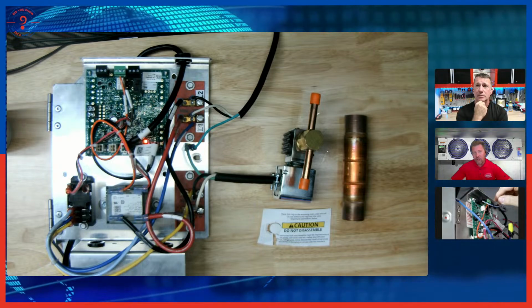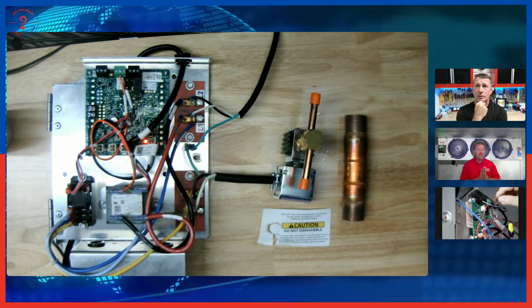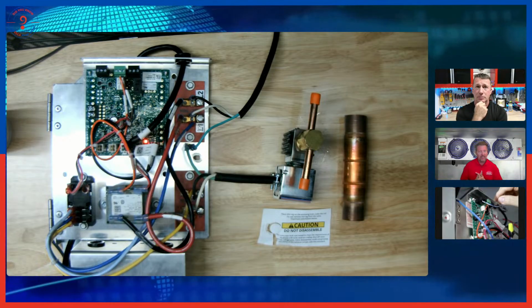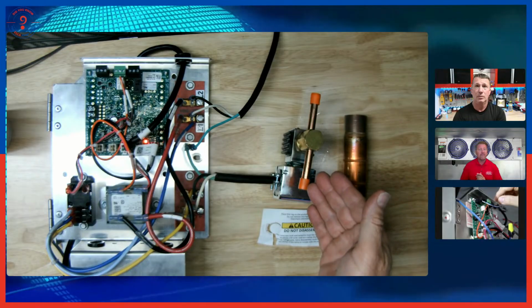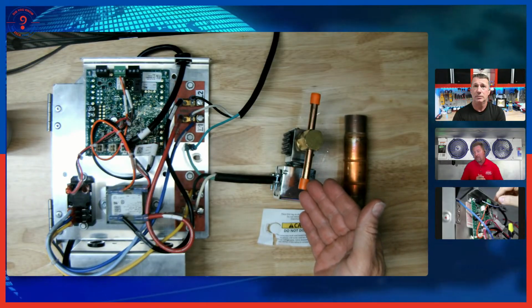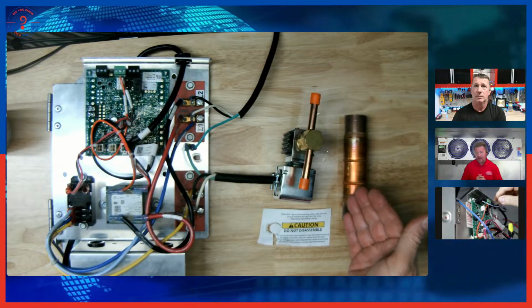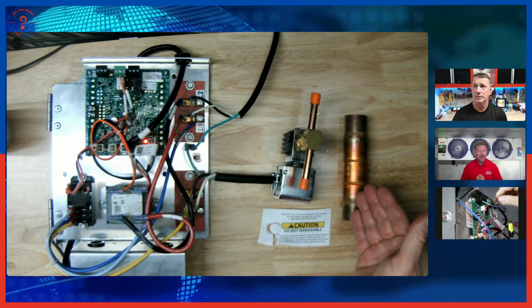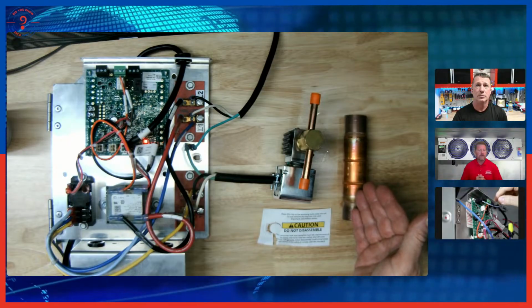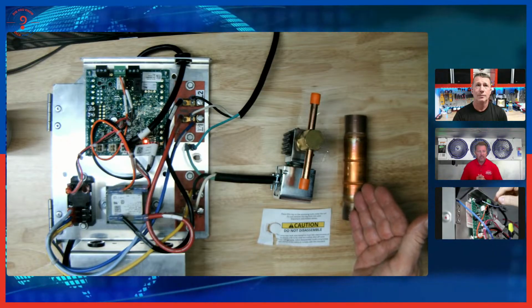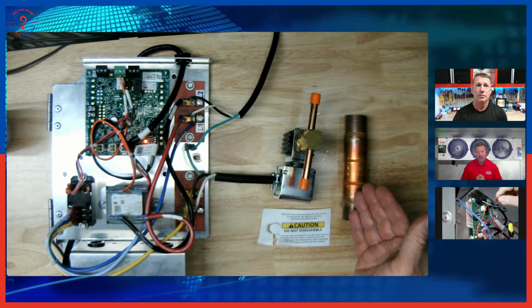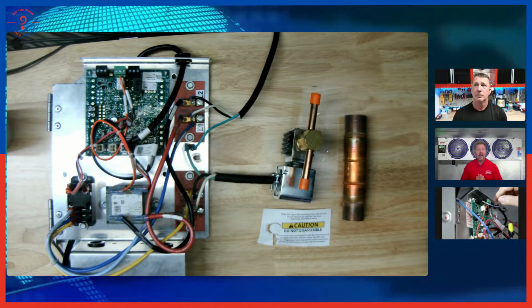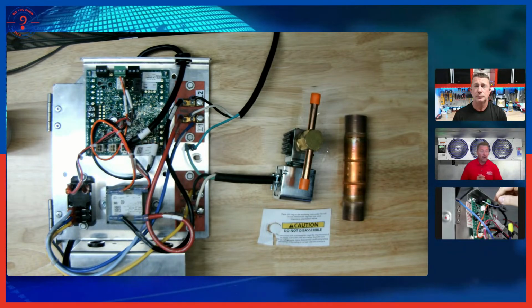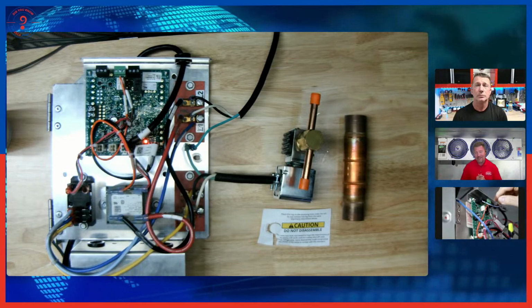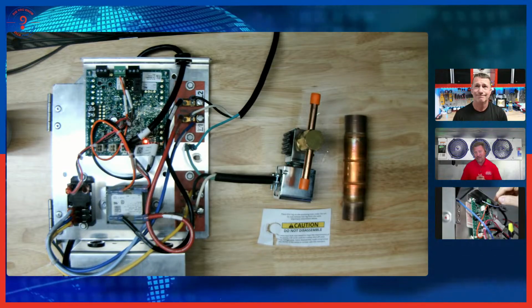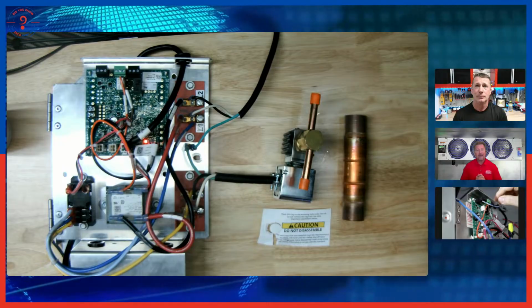Our RDS conversion kit, you will purchase these components as needed. Again, the RDS kit, your solenoid, you would purchase based off the voltage that's required. Right. Your check valve would be sized to your suction line. So again, one size never fits all in refrigeration. Exactly. With your salesperson or your local wholesaler, you would need to provide them that information, and we'll make sure that we get you matched up with the right stuff, to make sure that your solenoid is, one, large enough, and two, your check valve is not too small, so you're not causing a restriction in your suction line. Those things do matter. Yeah, absolutely.